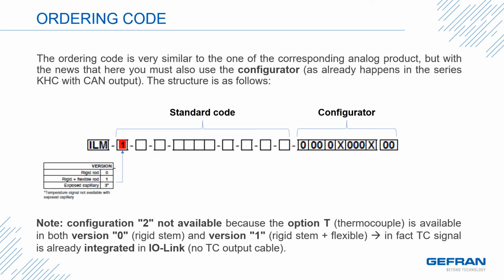If you are familiar with the Gefran melt pressure ordering code, you will notice that the IO-Link melt pressure ordering code follows the same flow. I will point out that the configurator or the extension code is required when ordering the IO-Link melt pressure sensors. Starting on the left, you'll see that this code, this example, starts with ILM, which is an IO-Link sensor with a mercury fill. The numeral 1 indicates that this model is going to have a rigid stem with flex.